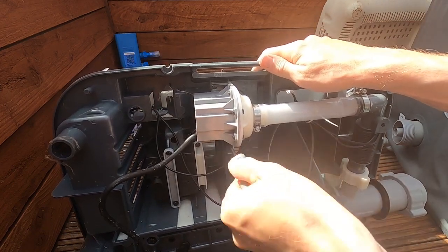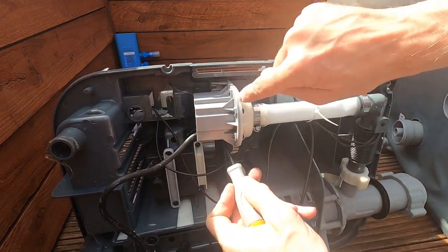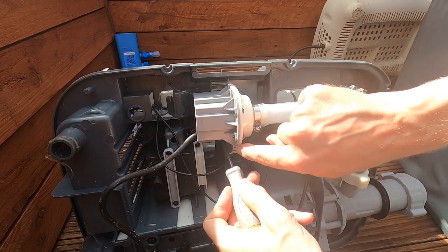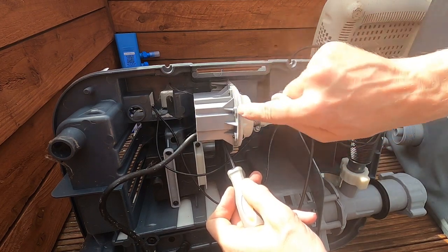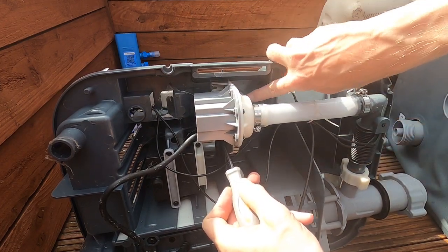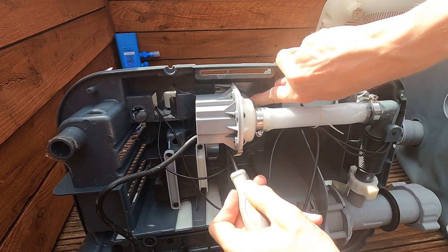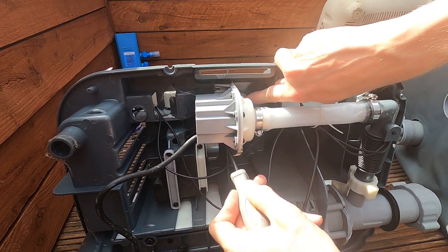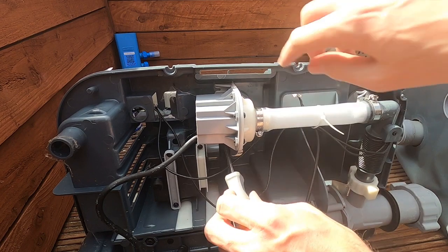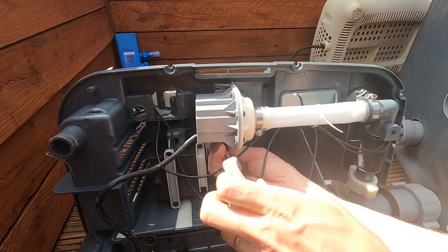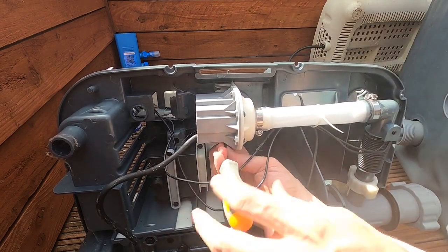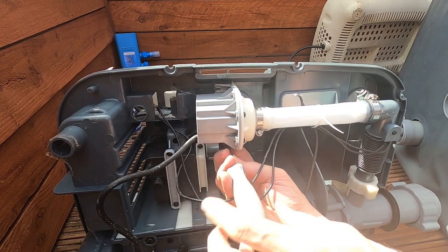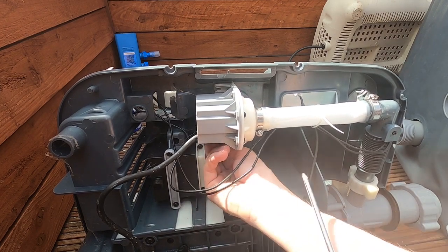What you can also get is leaks coming from this seam here, because there's a seal and a seam fitted there - that's quite common. Also around this piece, which is just a push-fit connector, again using seals into the heater, that's quite a common place too. So if you're getting water while your pump's running, this is normally a good place to start looking.